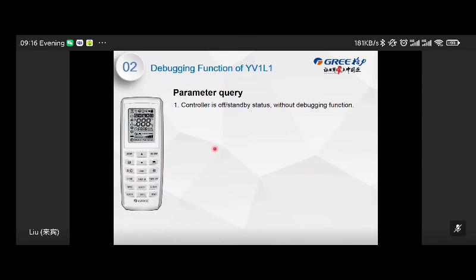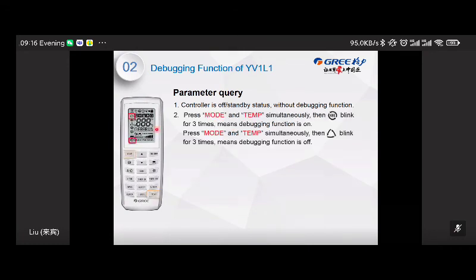So for the debugging remote, here is the parameter checking method. So the first one, make sure the unit is off or standby, and then press this button, mode and temperature simultaneously, and then this icon, space heating, blinks 3 times. Then press the mode and temperature buttons simultaneously again, and then this icon will blink for 3 times. That means the debugging function is off. Okay.